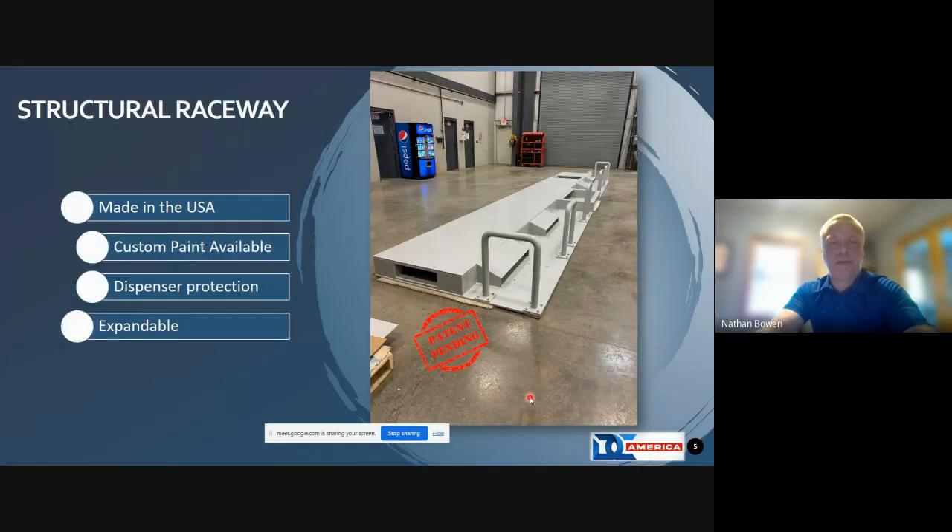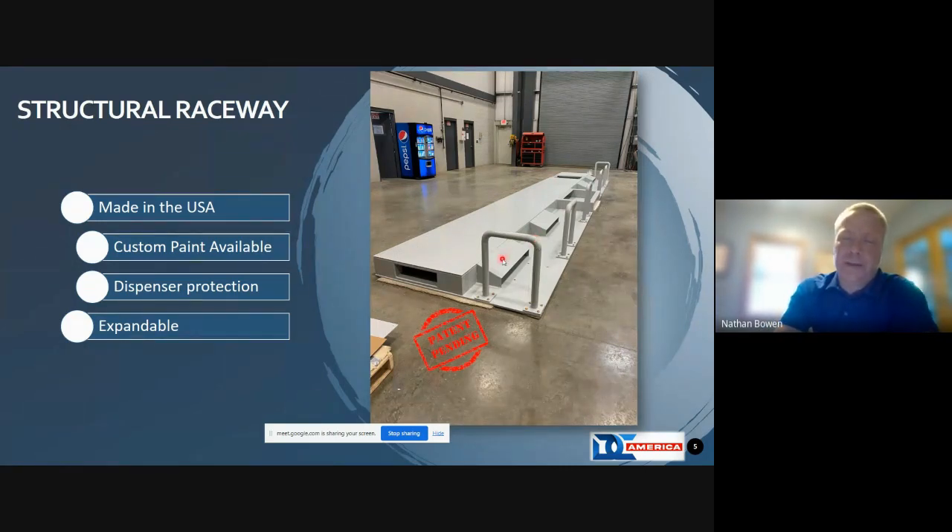The heart of our system is the structural raceway — all the cabling resides in this structure itself. Lifting hooks for cranes are all inside. These are removable quarter-inch diamond-plated plates, very heavy duty. You could literally drive a semi truck over them. Looking at the steel bracing — it's eight-by-six-inch steel tubing, and that actual bottom plate is three-quarter-inch plate steel, very sturdy. To meet ADA compliance we had to drop down the mounting arrangement for the charger dispensers to keep controls at 48 inches.